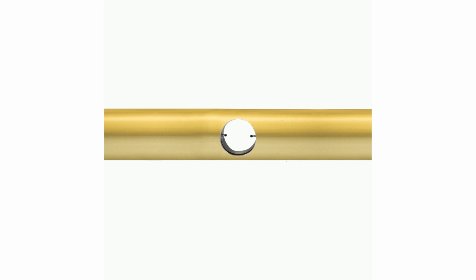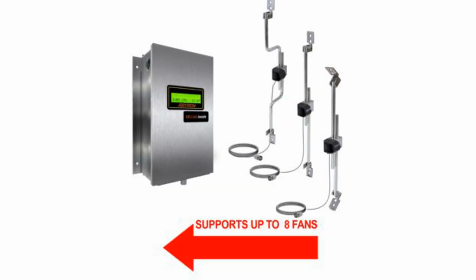The water flow measurement can be of, again, different types. It can be a turbine flow meter, electromagnetic flow meter, or ultrasonic flow meter. A turbine flow meter will have a tiny wheel. As your water flows, the tiny wheel keeps spinning and gives you, based on its own calibrated calculation of how fast the turbine was spinning, how much the flow was.